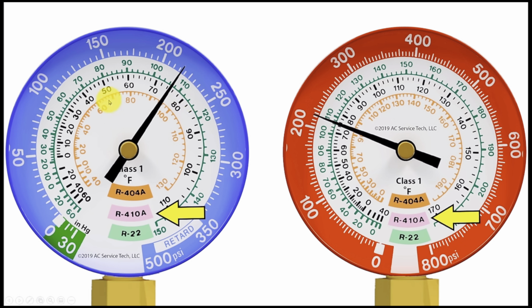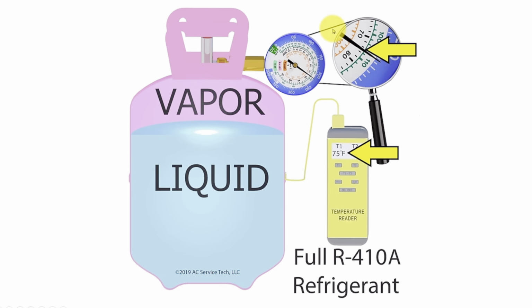Since we're focusing on 410A, we go to where the needle is, and we see in the black numbers it's just between 70 and 80, indicating 75 degrees saturated temperature. The gauges show the correlation between pressure and temperature. As the pressure goes up in the PSI, the temperature also goes up, and it's different for each refrigerant. For example, if I put a temperature gauge on a refrigerant tank and it's 75 degrees, I know that the saturated temperature of 75 degrees is 215 psi.